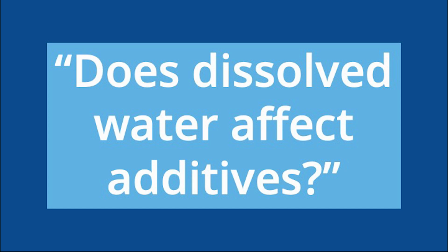And while we're talking about that, dissolved water also does have an effect on additives. Most definitely. One of the things that water is going to do to a lubricant, it's a contaminant. It's not supposed to be there. It is there. Any contaminant is going to accelerate the oxidation rate of the fluid.